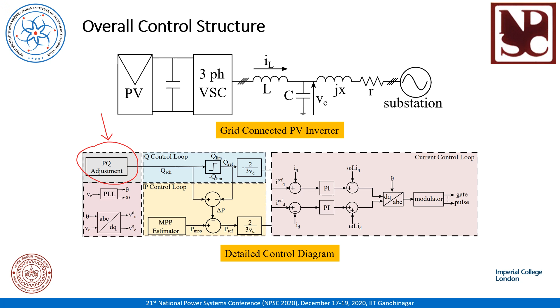The D and Q axis reference currents for the PV inverter are generated from this P ref and the Q ref. In the inner current loop of the inverter, the reference values of the current are compared with their actual values, and the error signals are passed through the PI controllers to generate the gate pulses for the inverter.